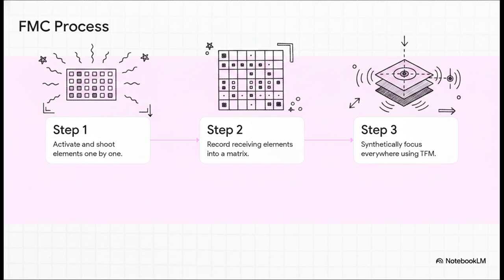Here is the step-by-step of how this actually works. Step 1. The system activates and physically fires each individual element one by one in a sequence. Step 2. It records the returning echoes from every single receiving element and dumps all that data into a massive raw matrix. Amazingly, it doesn't even need to know the shape of the part yet. Then, Step 3. This is where the actual magic happens. The total focusing method algorithm takes that massive grid of raw data and synthetically focuses the image at every single point in the region.